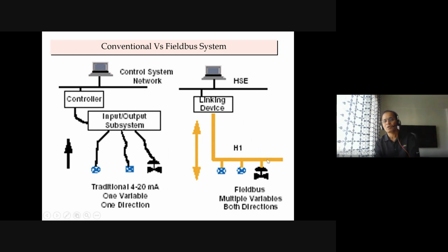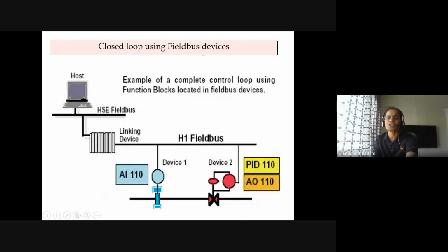However, in the field bus, what happens? A single wire, and the devices are multi-drop, linked to your DCS controller. So the advantage here is that the conventional signal is one-way communication, and control is also one-way from the output side, whereas this is bidirectional communication because it's a digital signal. If you see any field bus closed loop, how it is operating, this is a transmitter, this is a control valve. You see, this loop is here. So there is no need to be controlled through the DCS controller.